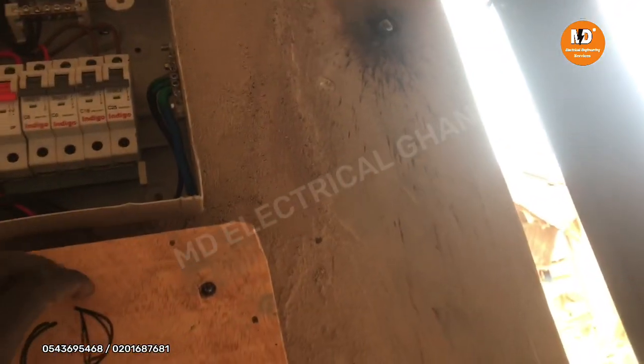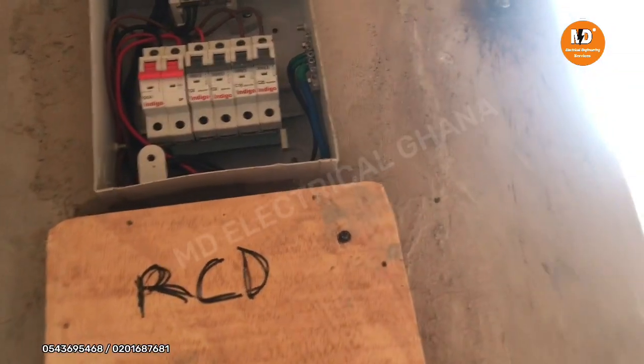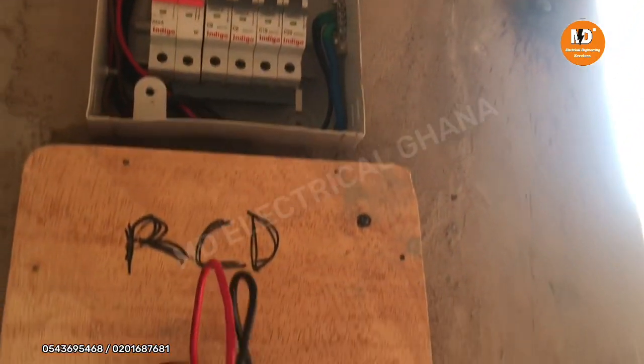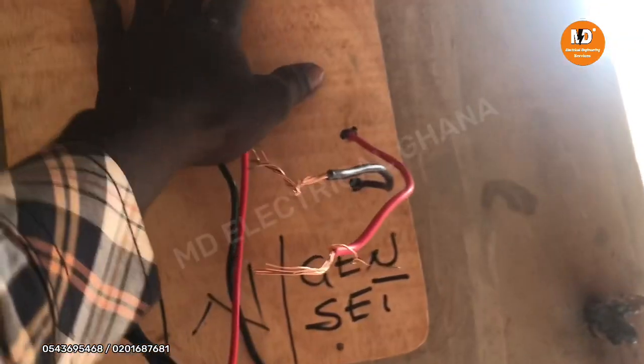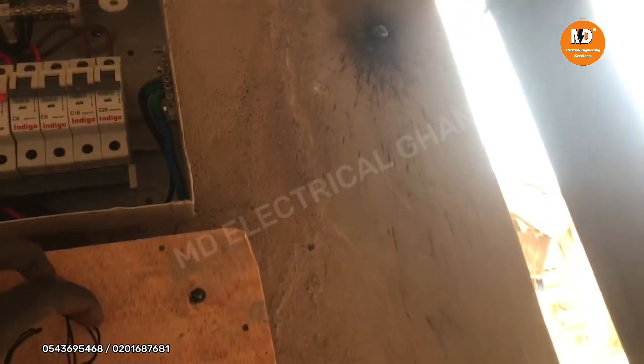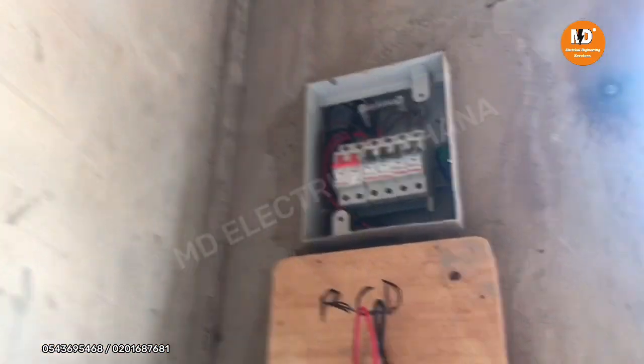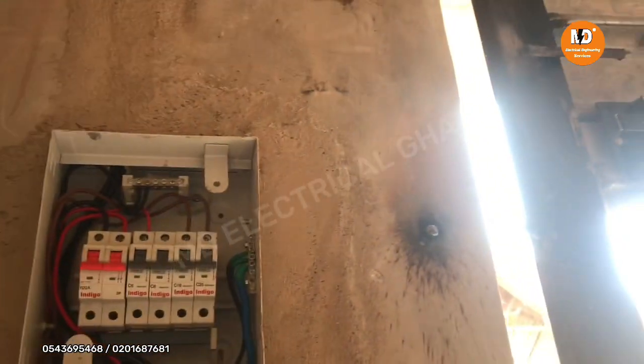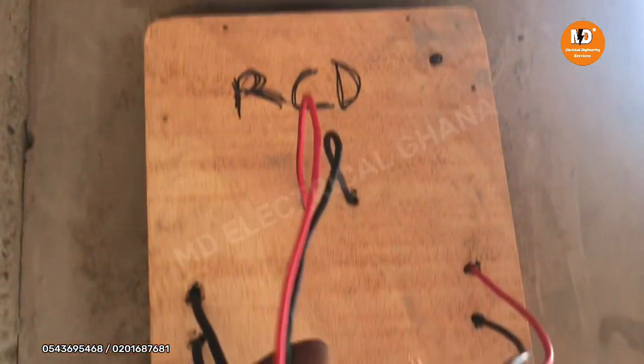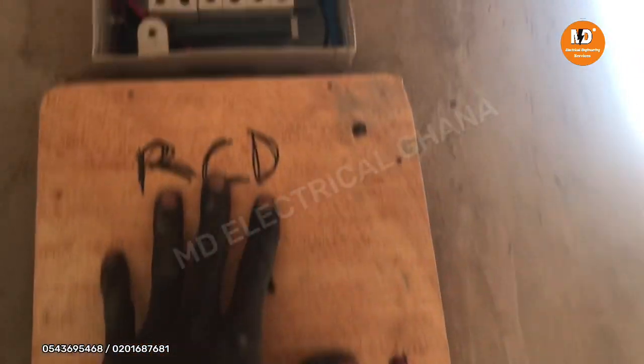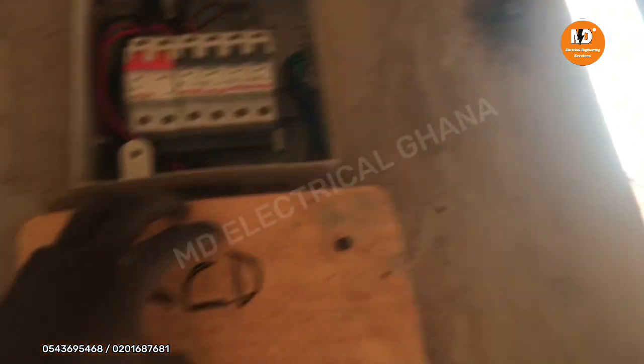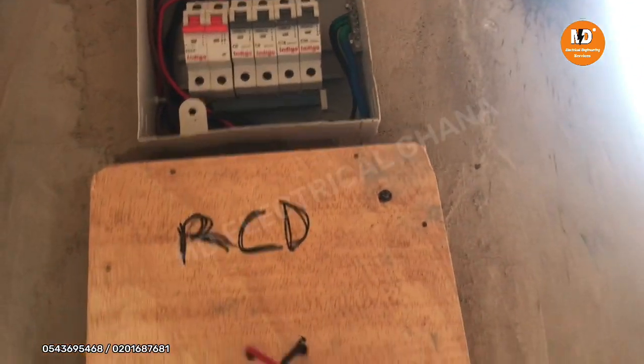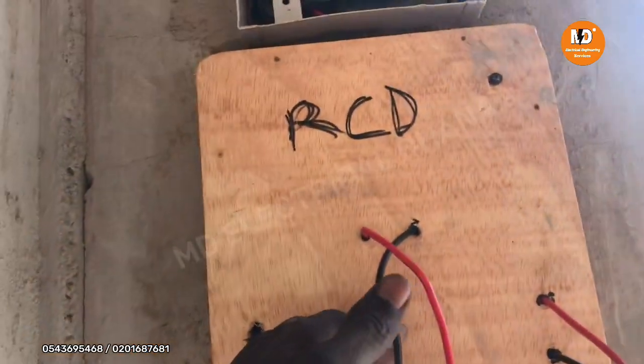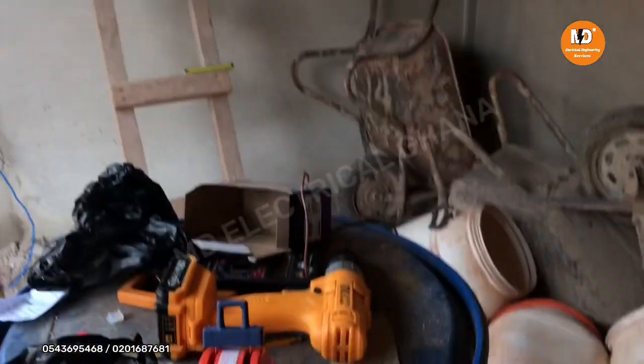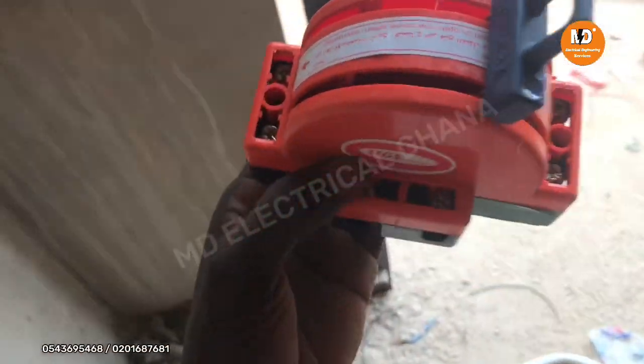The reason why we are fixing the RCD at the top there is because the consumer unit that we instructed our client to go for, he didn't go for that specific one, so he went for a different brand. This also works perfectly fine, but there's no provision where you can install your RCD. So in this case, we'll bring the RCD on the meter board, and below the RCD position you can see a couple of cables. That's where we're gonna fix our changeover. That's our single phase 2-pole 63 amps changeover switch.